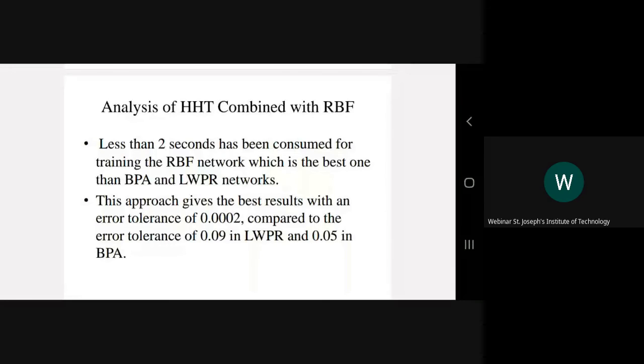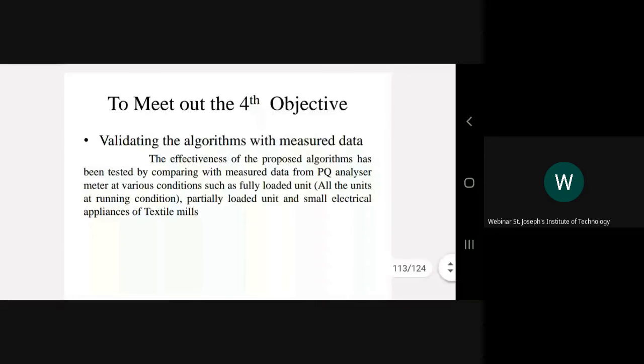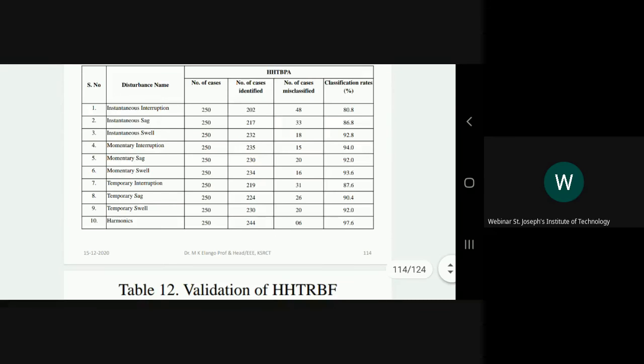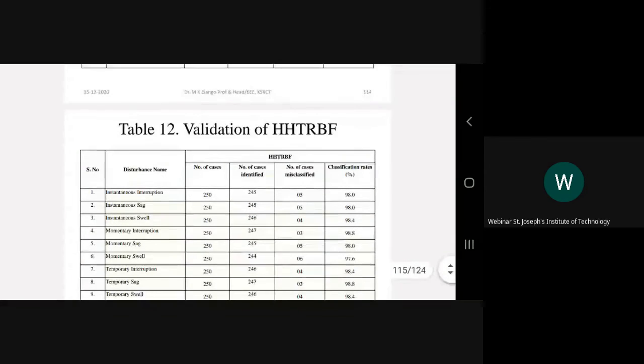To meet the fourth objective, validating the algorithm with measured data, the effectiveness of the proposed algorithm has been tested by comparing it with measured data from a power quality analyzer meter at various conditions such as fully loaded with all units running, partially loaded, and small electrical appliances of textile mills. The validation results for HHT BPA, HHT RBF, and HHT LWPR are given in the table.